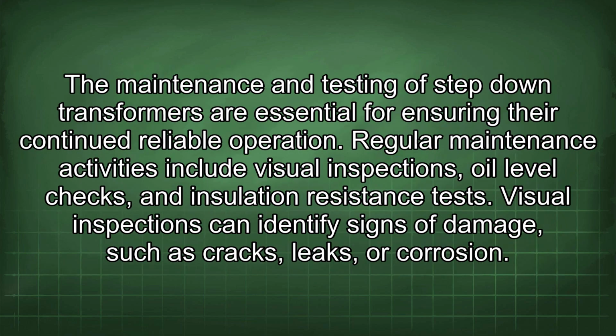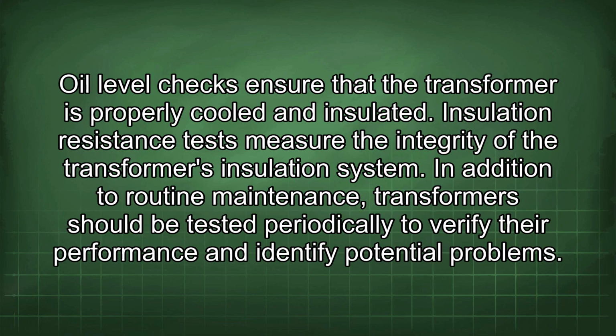The maintenance and testing of step-down transformers are essential for ensuring their continued reliable operation. Regular maintenance activities include visual inspections, oil level checks, and insulation resistance tests. Visual inspections can identify signs of damage such as cracks, leaks, or corrosion. Oil level checks ensure that the transformer is properly cooled and insulated. Insulation resistance tests measure the integrity of the transformer's insulation system.